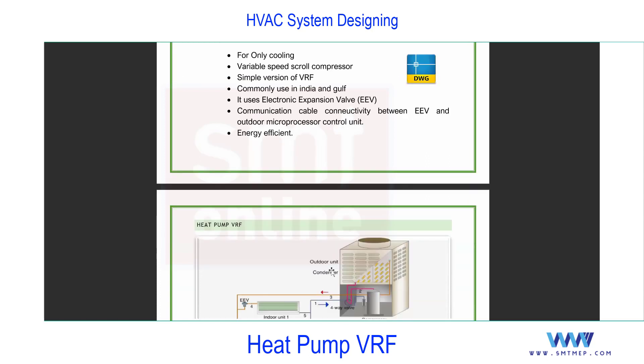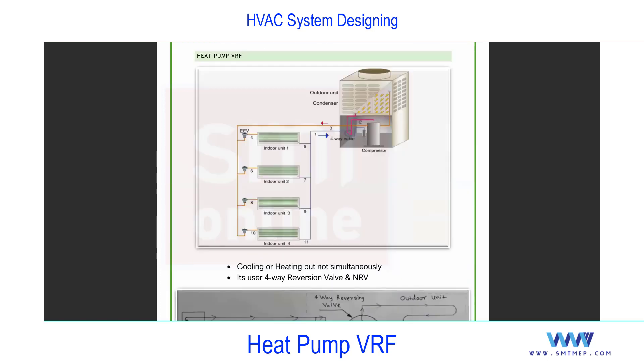Next we have a heat pump VRF. This is an interesting concept - when we use the term heat pump, we are talking about the vapor compression cycle but in reverse order. The condenser will change to the evaporator and the evaporator is used as a condenser. So inside the indoor unit you will find a condenser, and in the outdoor unit you will find an evaporator - that is heat pump mode.